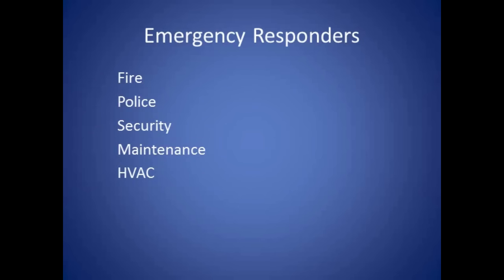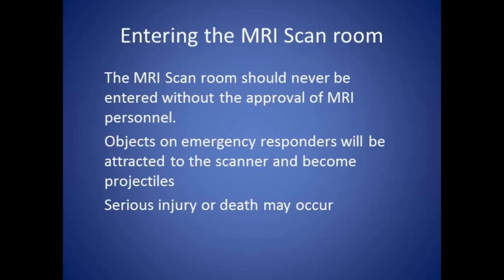There are many people that could respond to an emergency in the MRI department, all of whom need to be aware of the dangers associated with entering this unique area. The MRI scan room should never be entered without the approval of MRI personnel. Objects on emergency responders will be attracted to the scanner and become projectiles if they are ferromagnetic. Serious injury or death could occur.